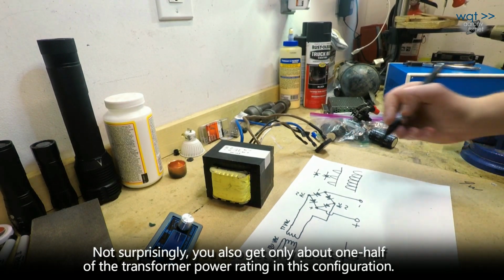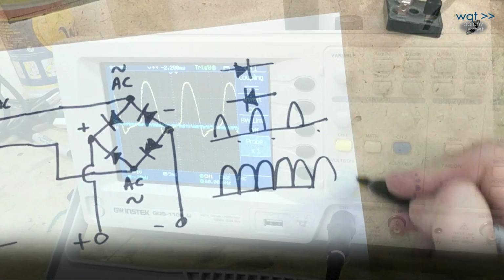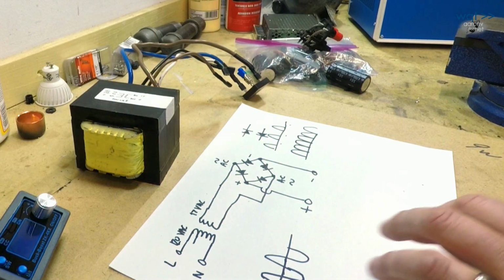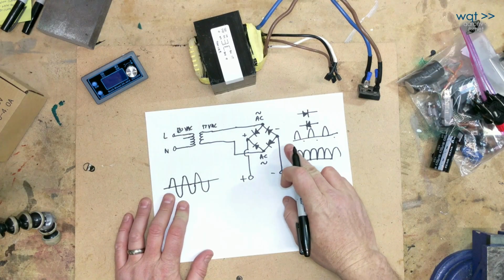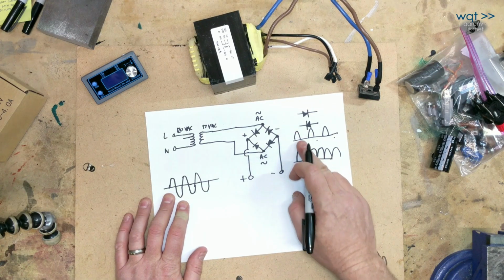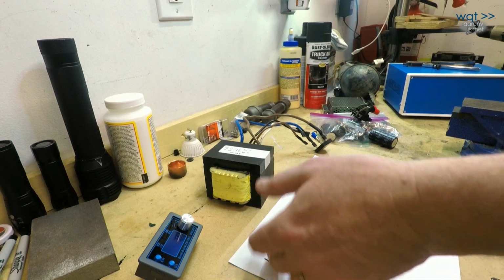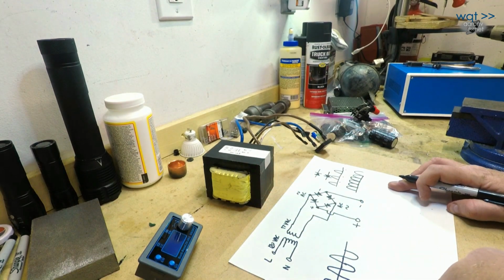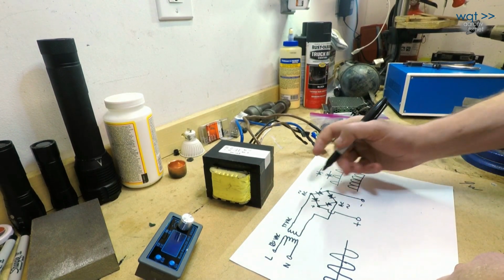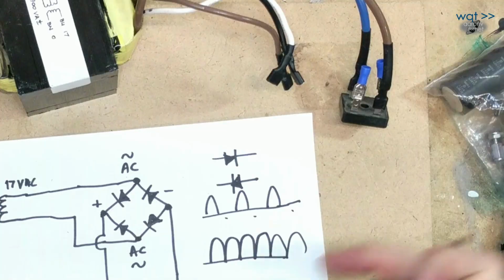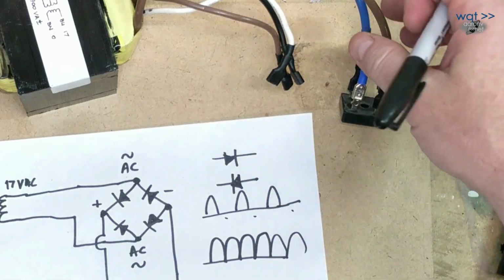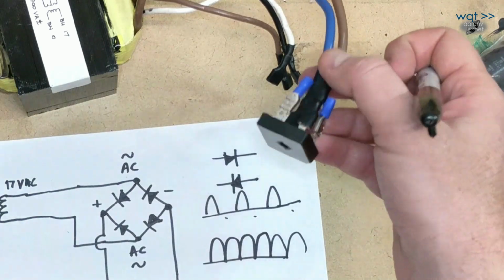That still works, but nothing's happening here, here, and here. Worse, you're probably getting some fairly nasty harmonics injected back into your power system, because on the positive waveform you'll pull current, and on the negative you won't, causing a lot of jostling of the signal upstream. This is the best possible configuration to use, and conveniently you can buy purpose-built devices that do it for you.